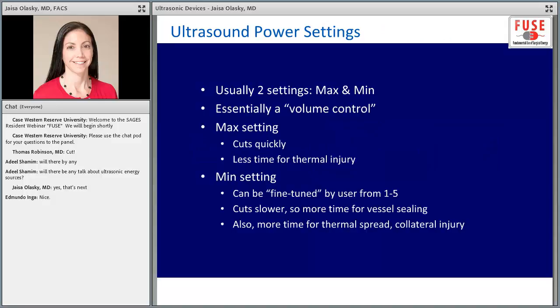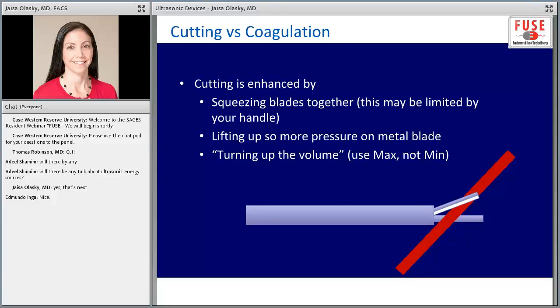Now moving on to clinical applications, when you're using the device, there's usually two settings, a min and a max. Generally the max setting will cut quickly, which is advantageous in that there's less time for thermal energy, and we do see less thermal spread than in other advanced instruments. However, if you do have any vessels within that area, there's very little coagulation on the max setting. The min setting, however, which can be fine-tuned from 1 to 5, cuts much slower, so there's more time for vessel sealing. There's also more time for thermal spread, however, and collateral injury.